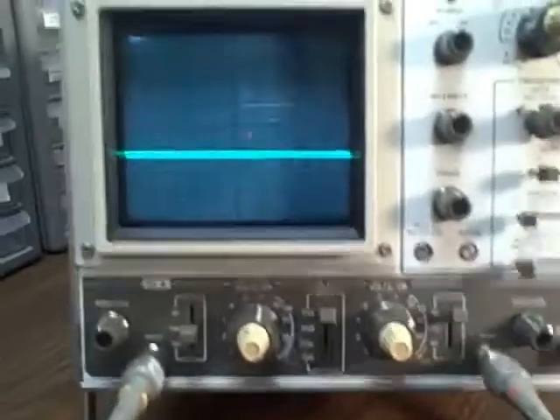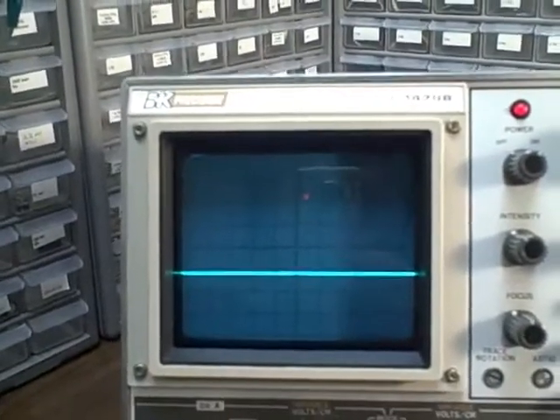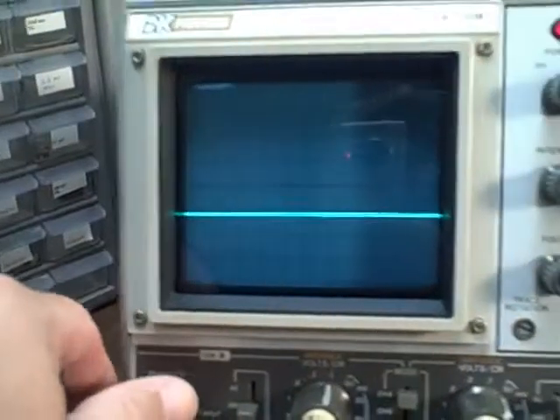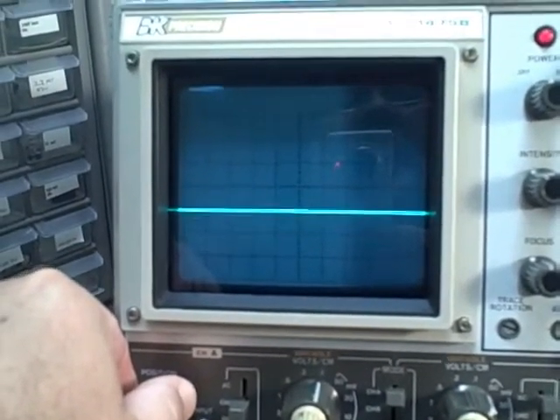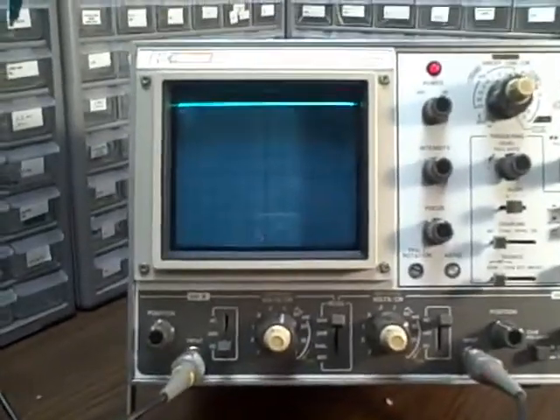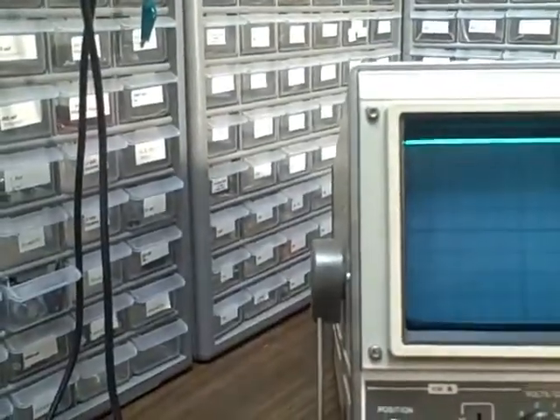Once I've proven that at 0.1 volts per division I rise my 5 divisions, I'm going to check my calibration output and see that it has 0.5 volts output as well, and then we're going to use that calibration point to check a number of scales. So once again, let's just make sure we zero ourselves. Alright, and then we're going to hit the DC, and we see that we instantly rise 5 divisions. Ground, 5 divisions.